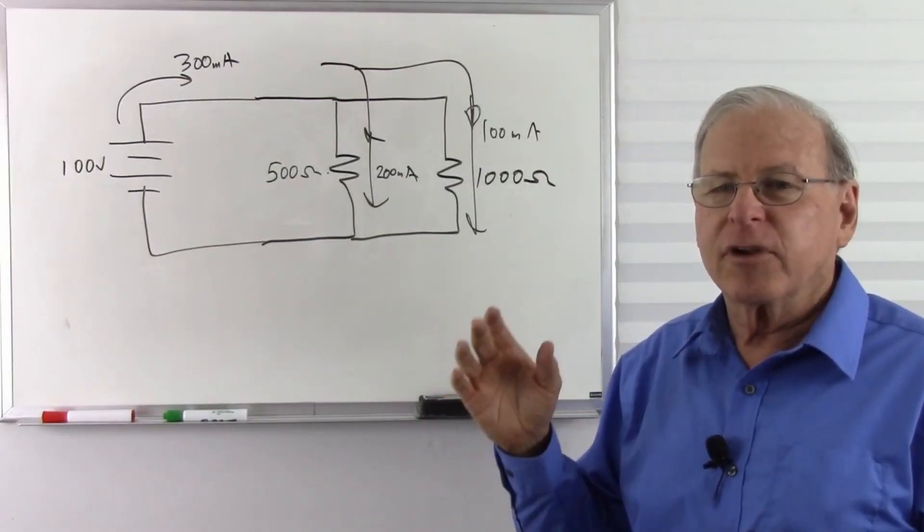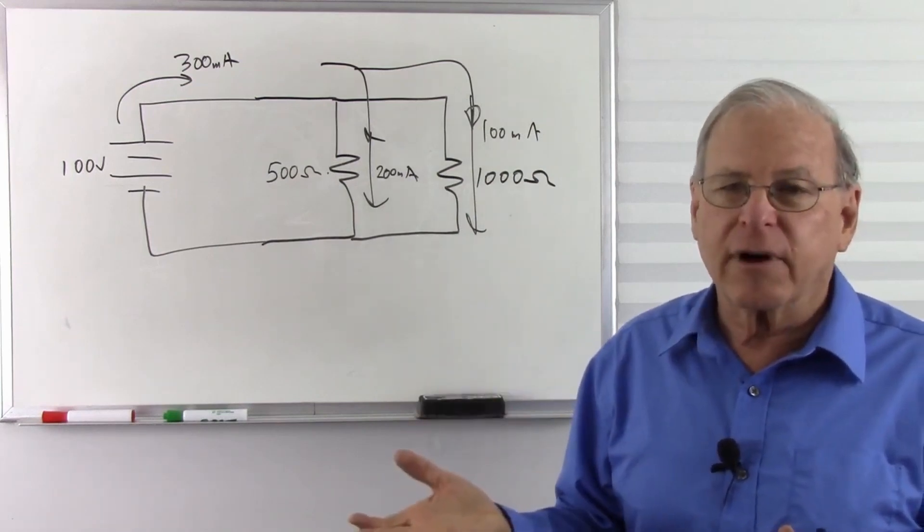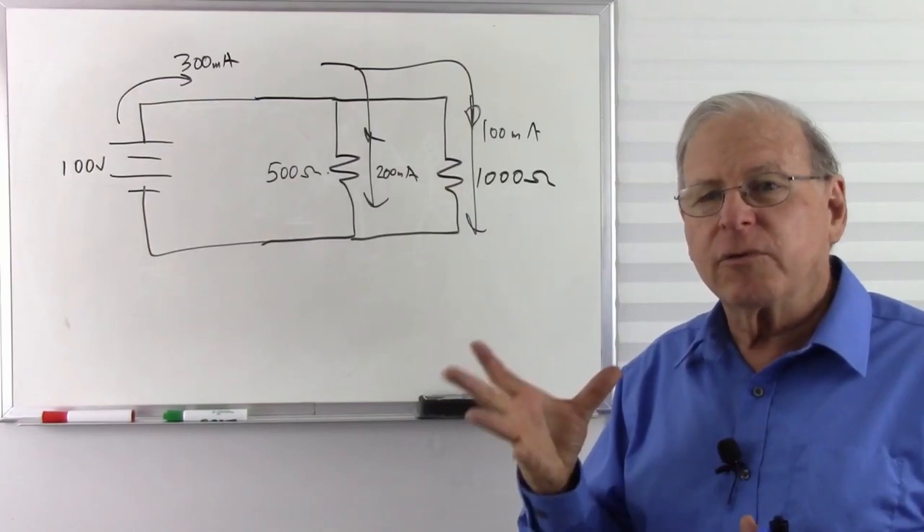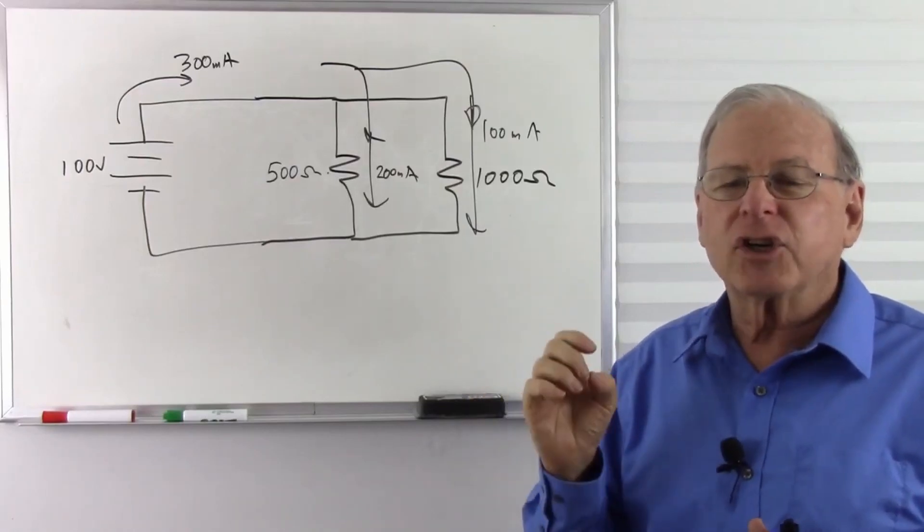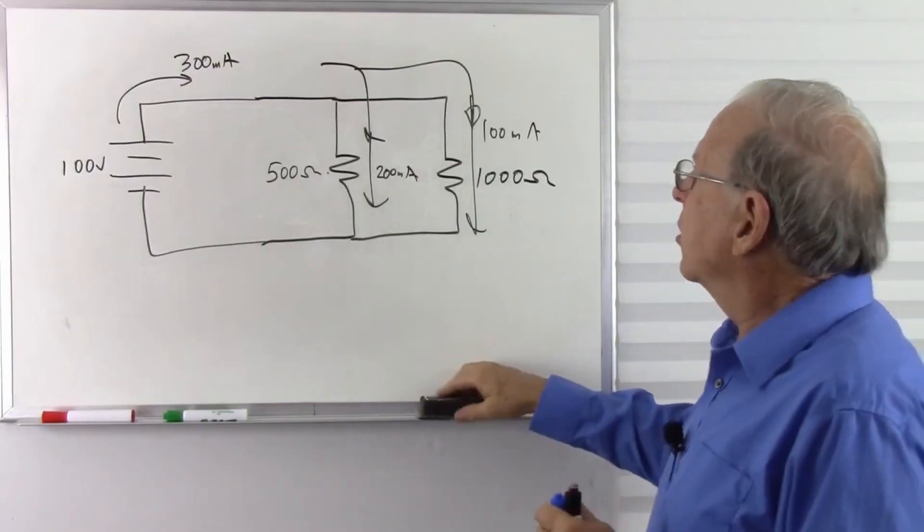And the second thing I was pointing out is grounding does not protect you because it creates a shorter path to ground. It's because the grounding wire has so little resistance that even with a large current going through it, it can't build up enough voltage to be dangerous. So let's take a look at that scenario.